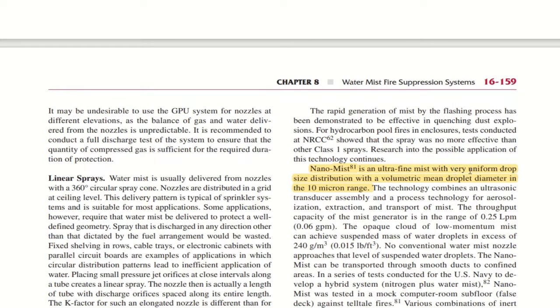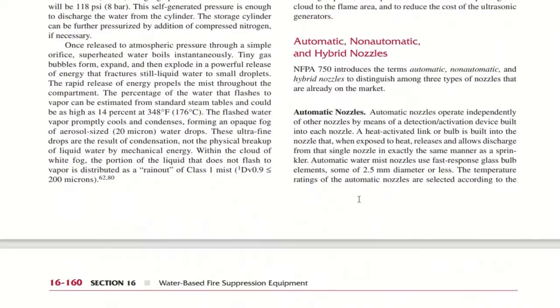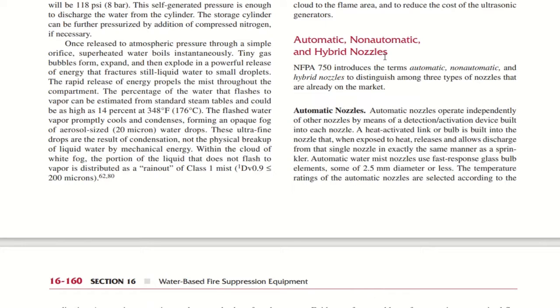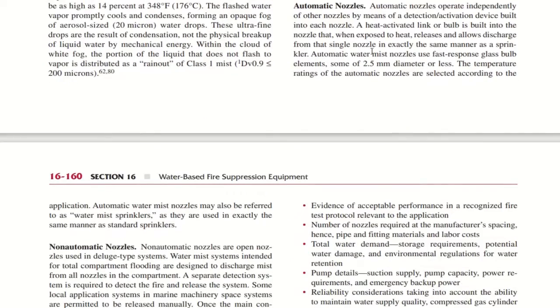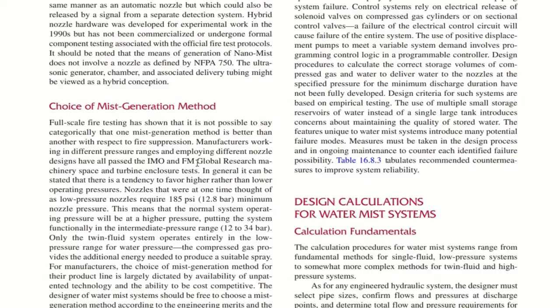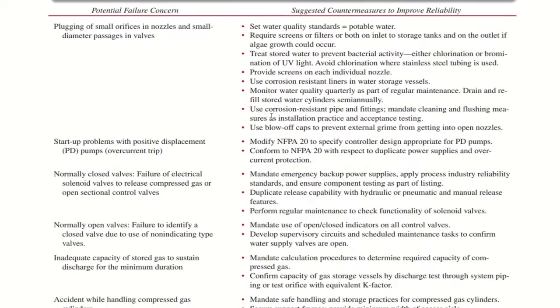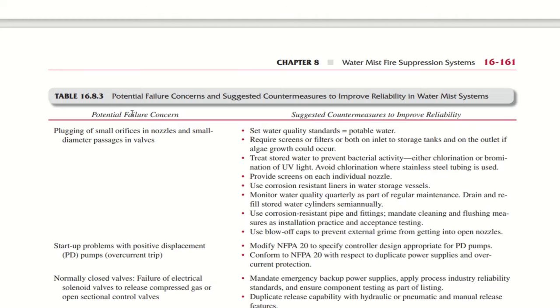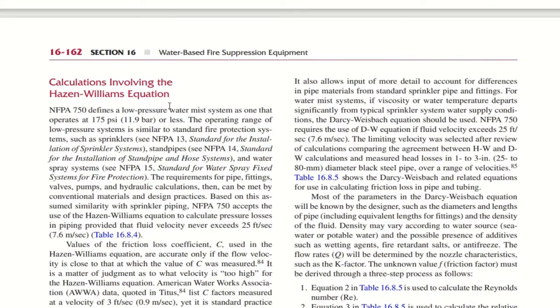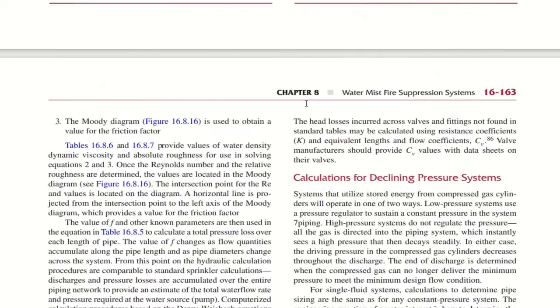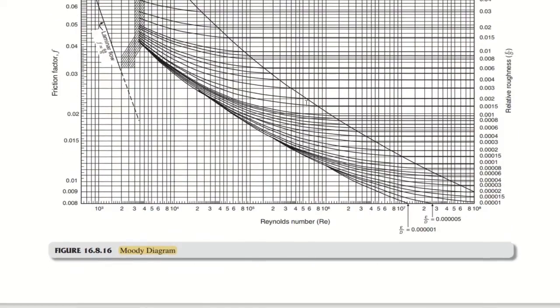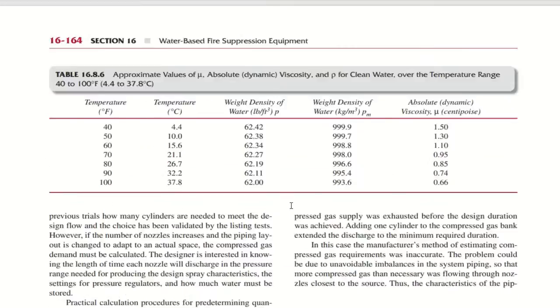Nano mist is an ultra fine mist with very uniform drop size distribution, with a volumetric mean droplet diameter in the 10 micron range. You have other kinds of nozzles such as automatic, non-automatic and hybrid nozzles. NFPA 750 introduced these terms to distinguish among three types of nozzles that are already on the market: automatic, non-automatic and hybrid nozzles. Design calculations for water mist systems. There are some fundamentals and there is a table which states potential failure concerns and suggested countermeasures to improve reliability in water mist systems. Calculations involving the Hazen-Williams equation, Darcy equation and Moody diagram are also available for water mist systems.